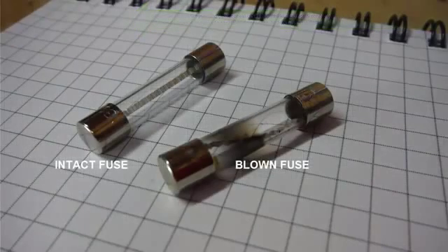When the fuse is intact, the path between its terminals is a closed 0-ohm path, and the circuit operates as intended. When opposition decreases and current reaches or exceeds a certain predetermined value for a certain amount of time, the fuse melts and the path between the two terminals opens and stops current flow by becoming an infinite resistance. The fuse is essentially acting just like a switch in series with the electrical device it is intended to protect.